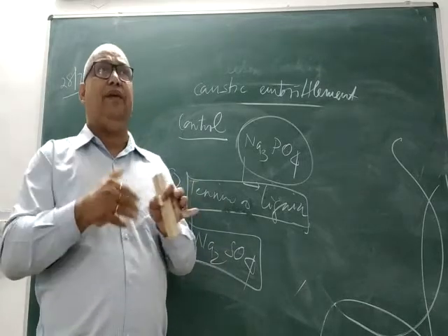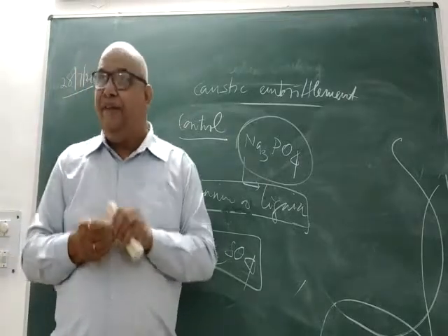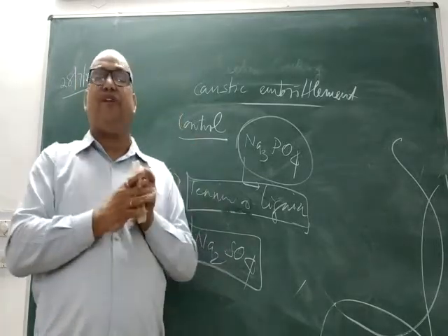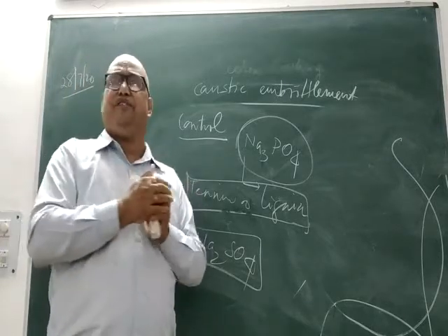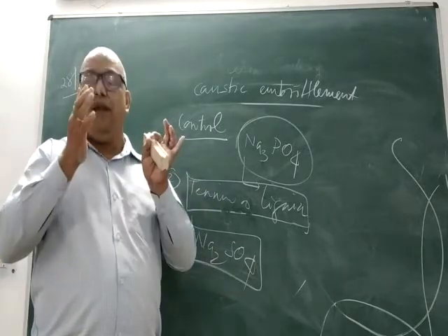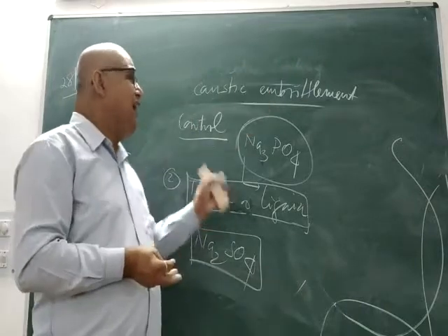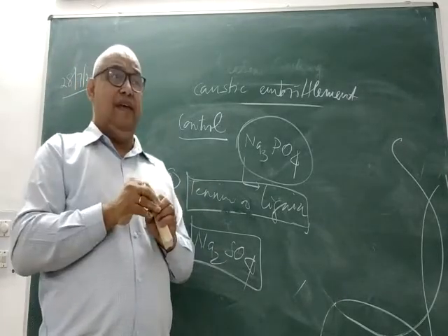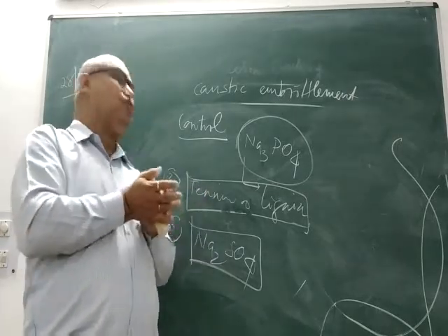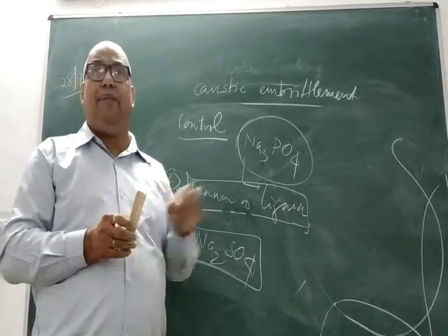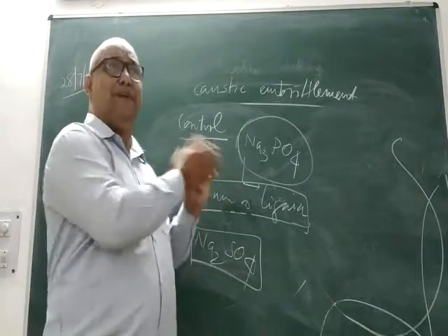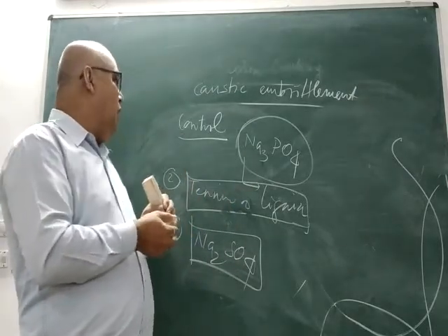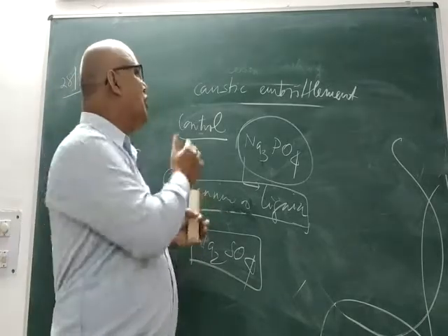But as we know, there will be some bend and joint in the boiler, and this bend and joint will make that area very, very stressed. In that situation, if sodium hydroxide is directly present in the water being used in the boiler, or sodium hydroxide is not there as such, but sodium carbonate is there, it will undergo hydrolysis, ultimately producing sodium hydroxide, which will make your water alkaline. And in this situation, if there is a hairline crack, it will get in contact there, and with time the water will evaporate, but sodium hydroxide will be concentrated there. Now the stressed area with a high concentration of sodium hydroxide will behave anodic, making the rest of the part cathodic. The electrochemical cell is completed because of the presence of a suitable electrolyte. Corrosion will take place, and iron will dissolve in the form of sodium ferrate. This kind of corrosion is known as caustic embrittlement.